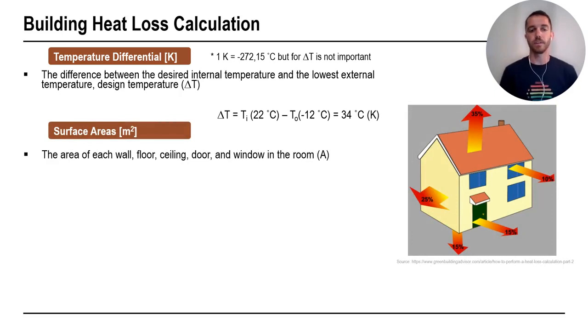Another point is surface areas in square meter. So this is surface area of our wall, floor, ceiling, or windows. In this example, or in this photo, you can see how heat loss is distributed through the building. So 35% is going through the ceiling, or the roof, 25% through the walls, 15% through the ground, 15% through the door, and 10% through the windows.